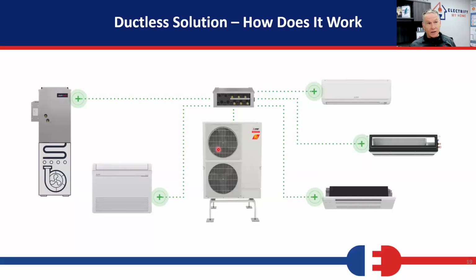However, in reality, what happens is I've got a 6,000 running in one room, or I've got that problematic room where the daughter is up in the front corner of the house where it's got the southwestern exposure and it's on 2 walls. Whatever. I've got that one room that wants to run all the time. This unit can only slow down to 18 or 20,000. I've got a 6,000 BTU unit going here. It's always going to put out 6,000 BTUs. It's never going to go less than that. In fact, it might overclock a bit.